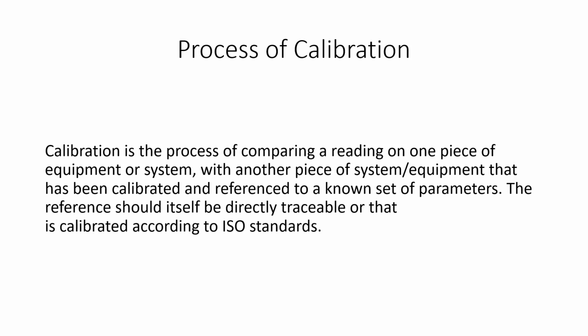Frequency depends on the equipment and the application. As a rule, however, calibration should be performed at least once a year, right? So this should be mentioned in the process of calibration: how much the frequency will be and when the calibration will be done. In more critical applications the frequency will be much greater. And for calibration, again, it is important that you have the proper reference, and the reference should be traceable or calibrated according to the ISO standards.